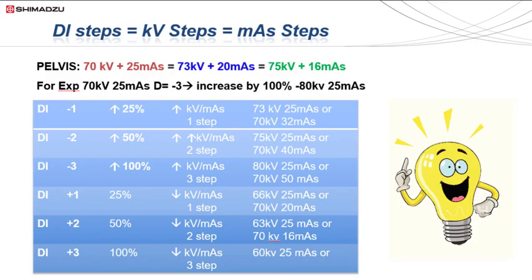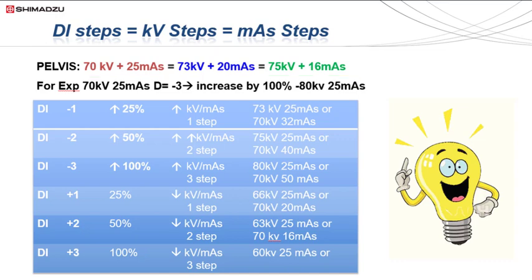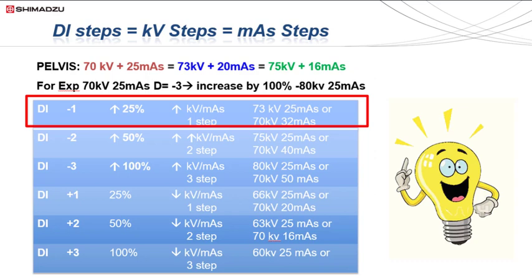To explain how to use these DI values and make them a functional tool, let's take a pelvic x-ray exposure as an example. We know that an exposure of 70 KV and 25 MAS is equivalent to 73 KV and 20 MAS, and is also equivalent to 75 KV and 16 MAS — for every step up in KV we make, we step the MAS conversely down. To increase or decrease the amount of exposure while keeping one factor constant: if we keep MAS constant and increase KV by 3 up to 73 KV, this is considered one step, or increasing the exposure by 25%, which is also equivalent to increasing the DI by 1.